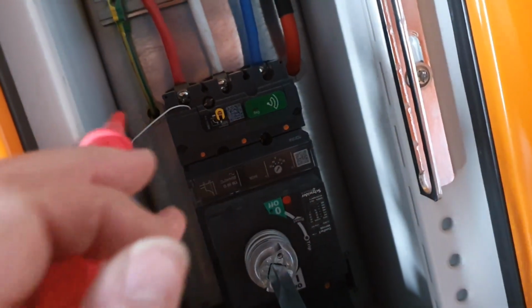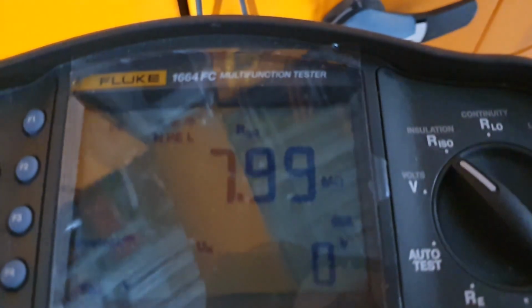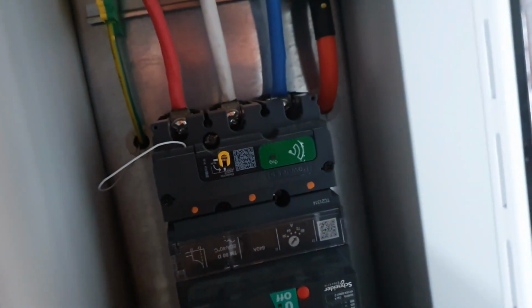Right, so that unit there, we'll zoom in a little bit so you can see, but if we focus - it's called a power tag, so it's a Schneider, it's got a little tail that shoots off. Now that gives you a bad reading on the insulation resistance. That gives you about 8 mega ohms, so it's not a problem because as soon as that turns on, it clears itself. It's not an issue.